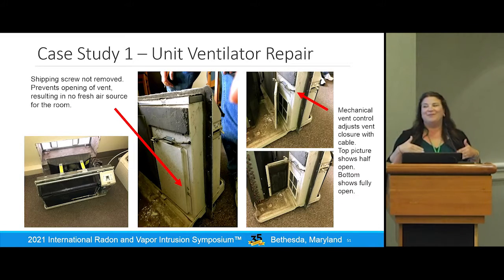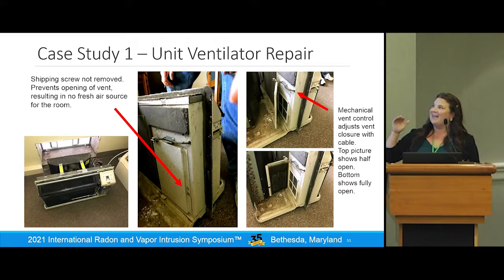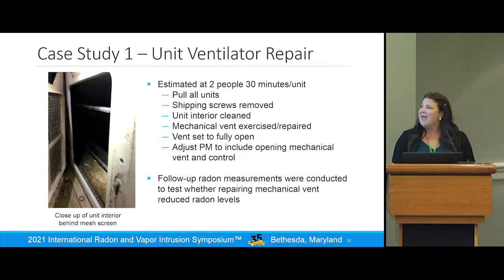We pulled all of the units and found shipping screws that were never removed from when they were installed. That vent had never been opening, so these poor people living in the barracks were never getting any fresh air into their rooms. The shipping screws were removed, and we made sure the mechanical vent control could open and close. Here's one more close-up picture of the interior of the ventilator behind the mesh.